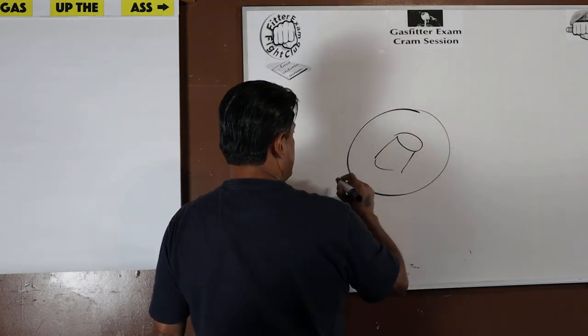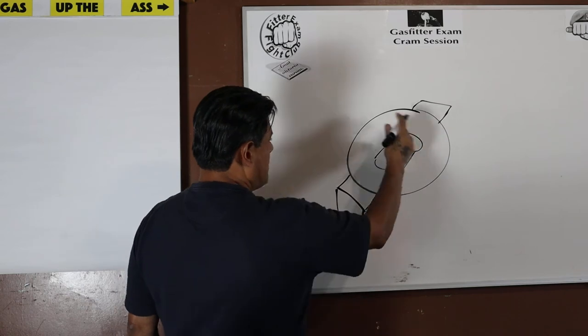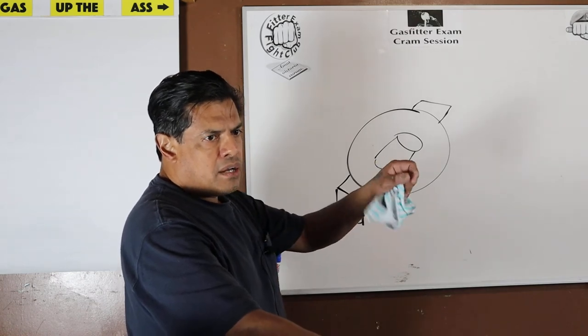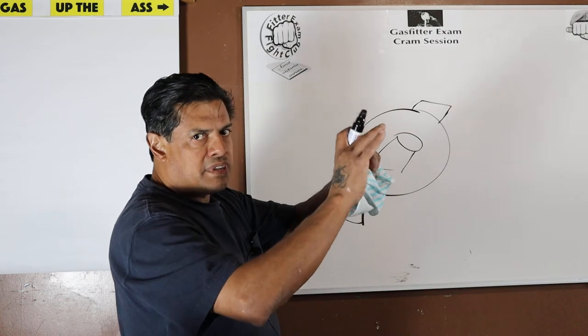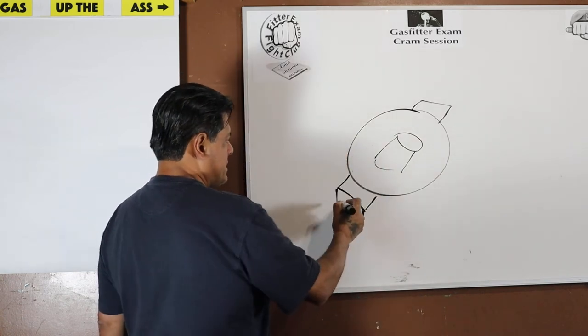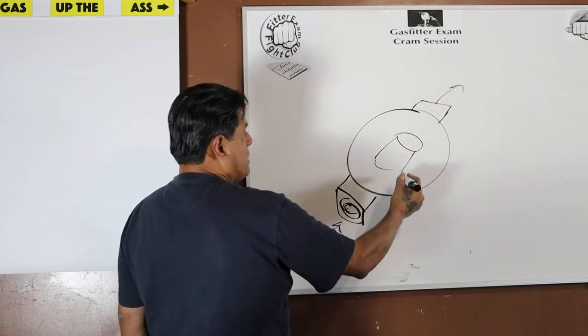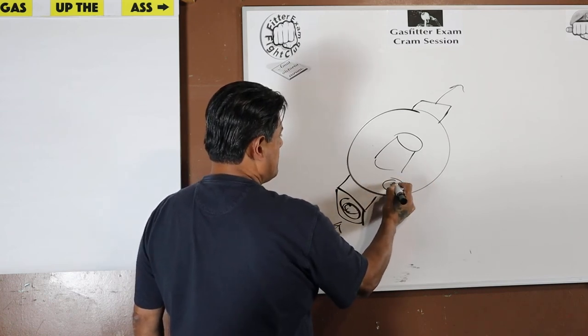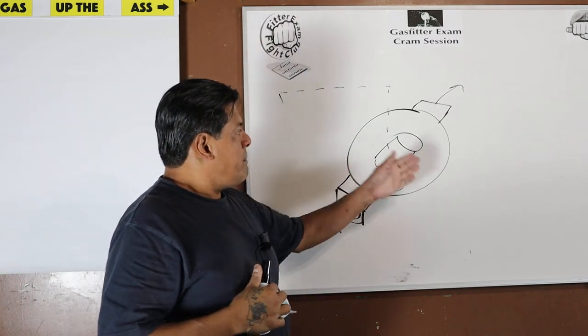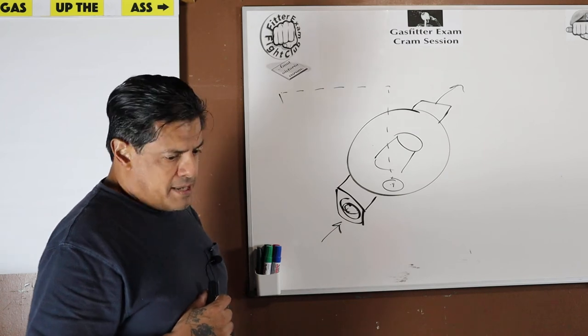the next time you are working on gas, you can take a look at it and see that the round thing, the regulator, is just like if you're working with an oxyacetylene setup and you have to adjust the pressures for your oxygen and acetylene. It's round, there's a diaphragm in there, turning the screw either increases or decreases the pressure. Exact same principle, okay? And here, you screw in your pipe, whatever. This is the regulator. There's a bossing or a tapping here, and you're going to run your vent. This is your basic setup. This vent, no matter how much gas leaks or escapes, this vent is going to take care of it, okay?